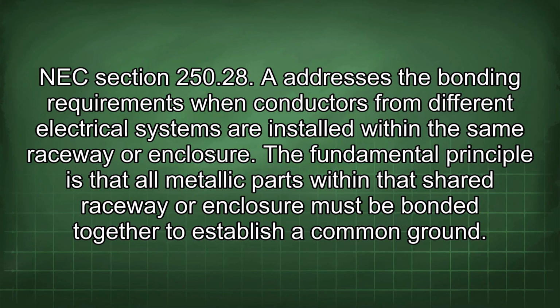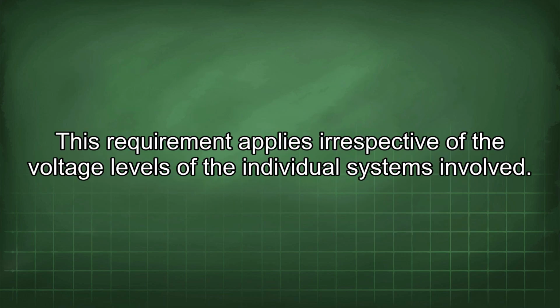NEC Section 250.28 addresses the bonding requirements when conductors from different electrical systems are installed within the same raceway or enclosure. The fundamental principle is that all metallic parts within that shared raceway or enclosure must be bonded together to establish a common ground. This requirement applies irrespective of the voltage levels of the individual systems involved.